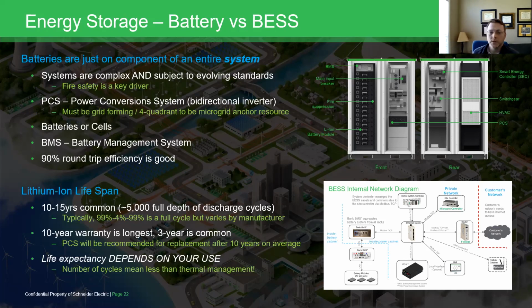Now, I expect those durations to be extended as battery degradation gets better and as inverters are pushed to match that battery degradation better, similar to what we've seen happen in the PV industry, with inverter warranties and lifespans more closely matching module lifespans. But the important thing is the life expectancy depends on your use. A lot of people want to use the number of cycles as an indication of how you're using the battery, and I would argue that's not the best way.